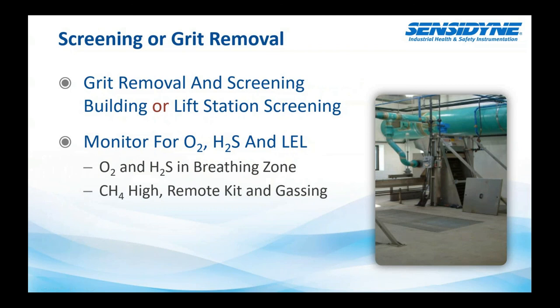Screening and grit removal areas. At lift station screening, you're going to monitor for O2, again in the breathing level, H2S, and then methane or LEL. And we can do remote mounting here. If this were a smaller room or you had an entry close by, we could monitor remotely with the sensors and then put the transmitter, be it an all-in-one with the annunciation, or a transmitter that goes back to a control panel of some sort with some kind of local annunciation. We could put that on the outside of the room. So as the employees are entering the room, the hazards are known in the room before they enter.